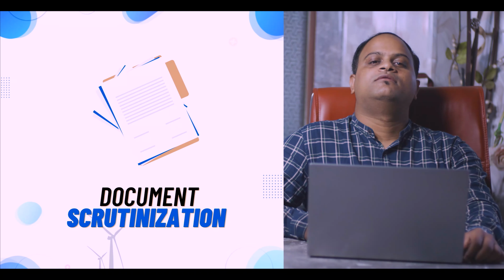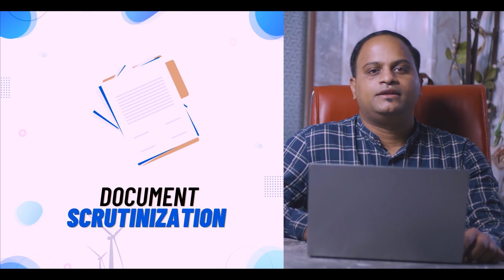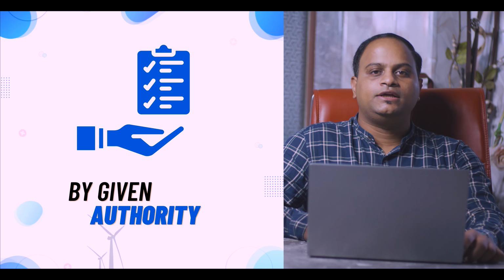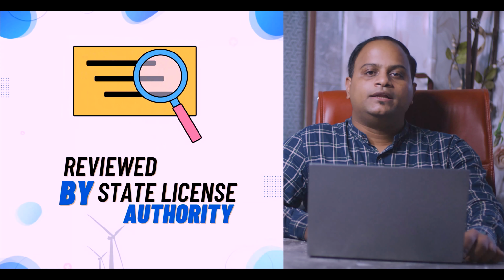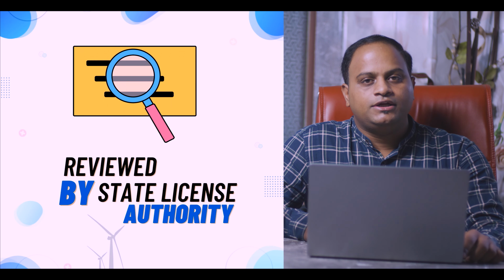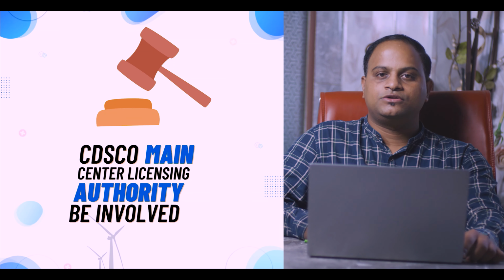After that, the documents are scrutinized by the given authority. If your product falls under class A and B, your documents are reviewed by the state licensing authority, and if it falls under class C and D, then the CDSCO central licensing authority is directly involved in this process.